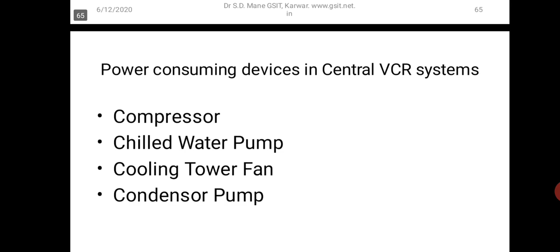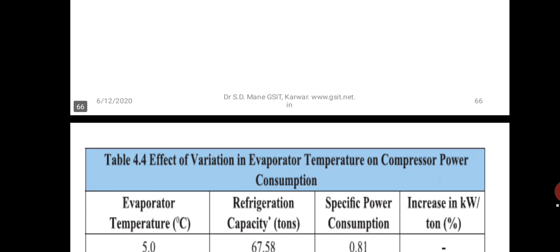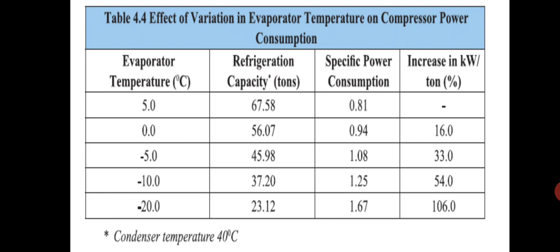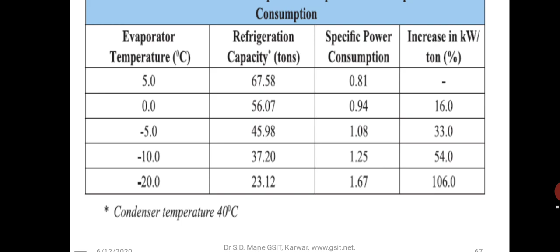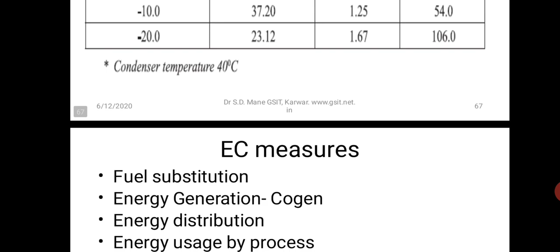And for HVAC you have the compressor, chilled water pumps, cooling tower fan and condenser pumps. Now, I think you are all aware that due to COVID, the government has asked people to raise the temperature of the ACs from 25 to 30 degrees centigrade. Just see column 1 and column 3. Column 1 is the evaporator temperature and column 3 is the specific power consumption. As you lower the evaporator temperature from 5, the specific power consumption increases. So this is not advantageous. That is why they are now advising to increase the evaporator temperature so that the specific power consumption is reduced, and it also takes care of this COVID sanitization business.